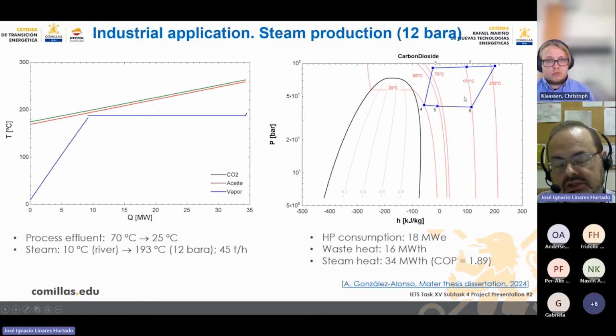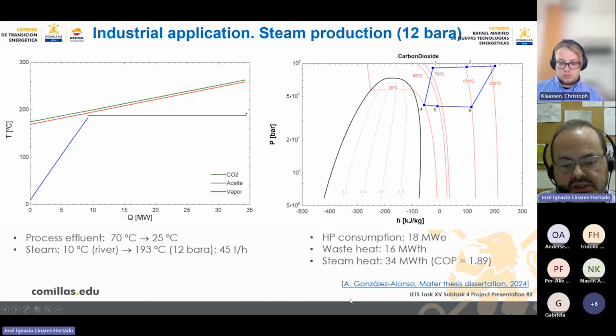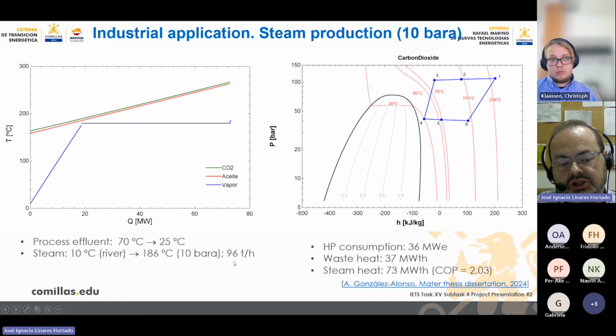And this is the scheme, this is the P-h diagram of the heat pump. This is a very large heat pump. As you can see here, we are producing 34 thermal megawatts with 1.89 value for COP. Okay. In this case, the mass flow rate of the steam is 45 tons per hour. And with the other pressure, we are producing more or less double, 96 tons per hour, and we are producing more than 70 thermal megawatts with a slightly higher COP, by more than 2 points. Okay.